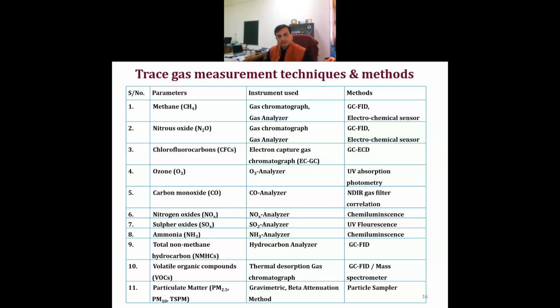Nitrous oxides are also measured by gas chromatography and a gas analyzer. Chlorofluorocarbons are measured by electron capture gas chromatograph. Ozone is measured through the ozone analyzer, and carbon monoxide through the CO analyzer, which uses the non-dispersive infrared gas filter correlation method. Nitrogen oxides are measured through the NOx analyzer, sulfur dioxide through the SO2 analyzer, and ammonia through the ammonia analyzer. Total non-methane hydrocarbons are measured by the hydrocarbon analyzer, and volatile organic compounds through the gas chromatograph. Particulate matter PM2.5, PM10, and total suspended particulate matter are measured by the gravimetric and beta attenuation method, called a particle sampler.